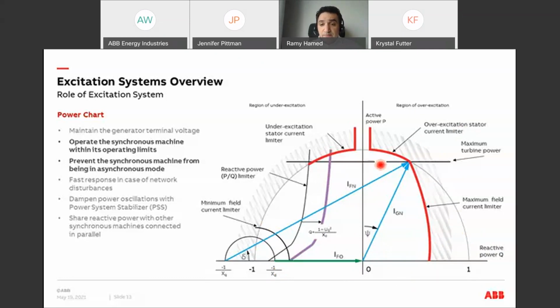In the over-excitation area, the main limit is the maximum field current, or the maximum current that the generator rotor can handle. Simply beyond this limit, the rotor will be damaged. On the other side, in the under-excitation area, the main limit is the PQ limiter, or the stability limit. And simply beyond this limit, the unit becomes unstable. And so we define these limits in the excitation system, and it becomes one of the main functions of the excitation system to maintain the generator working in that safe area between these two limits.